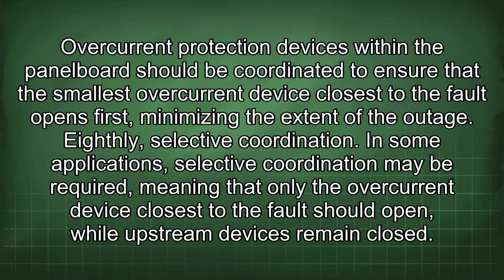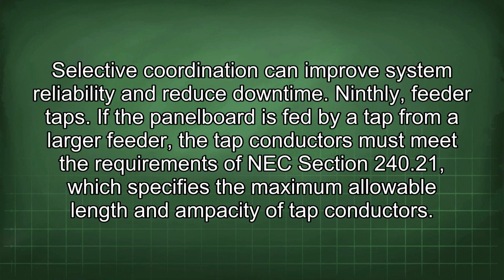In some applications, selective coordination may be required, meaning that only the overcurrent device closest to the fault should open while upstream devices remain closed. Selective coordination can improve system reliability and reduce downtime. Ninthly, feeder taps. If the panel board is fed by a tap from a larger feeder, the tap conductors must meet the requirements of NEC Section 240.21, which specifies the maximum allowable length and ampacity of tap conductors.